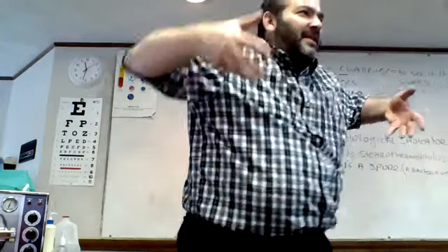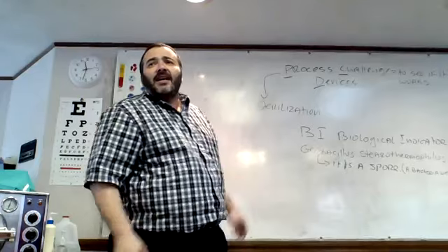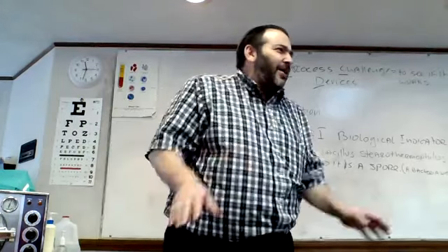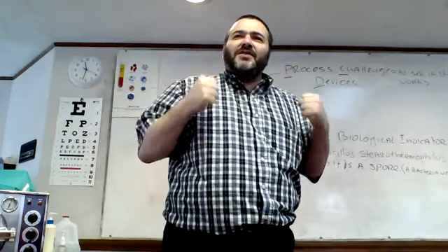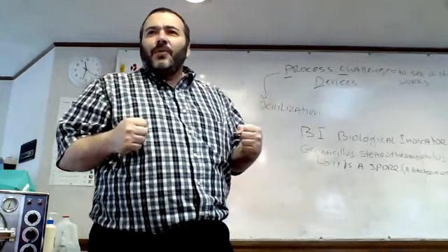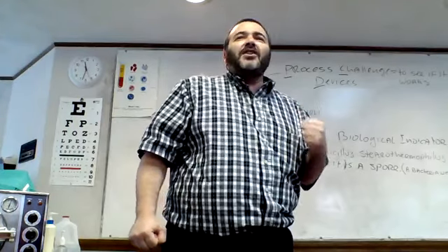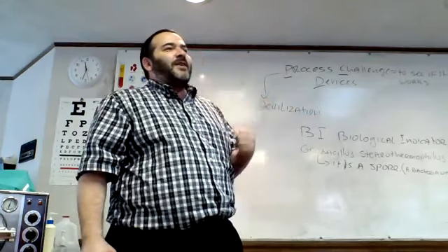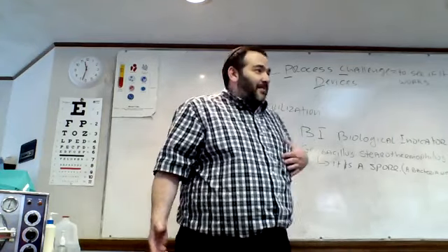We need to make the steam penetrate inside of a pack. It needs to be by that chamber drain, so it's the hardest place. If the steam goes in there, we have really pushed our process of sterilization to the brink. We want to make sure that the darn thing works, doesn't it? So we want to kill the most difficult thing. If we kill the most difficult thing, then the easier microorganisms are done as well. Make sense?